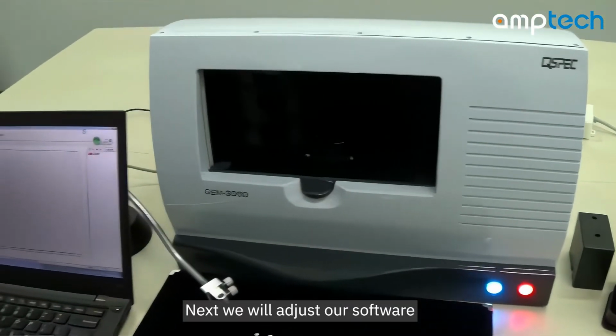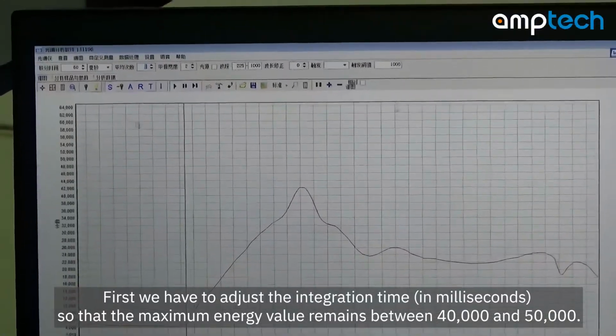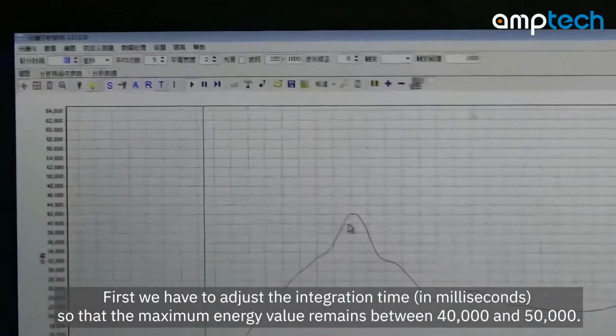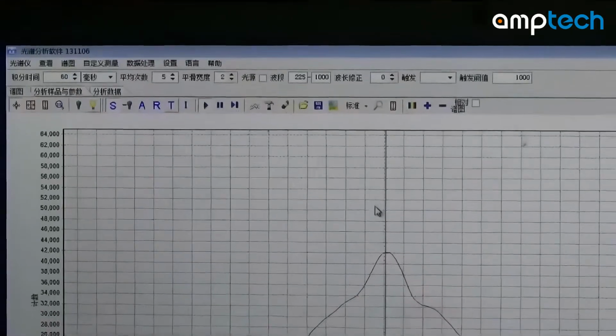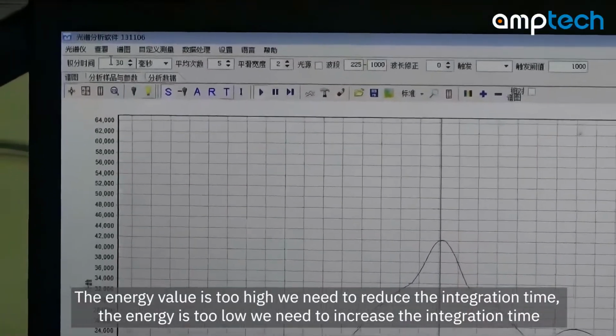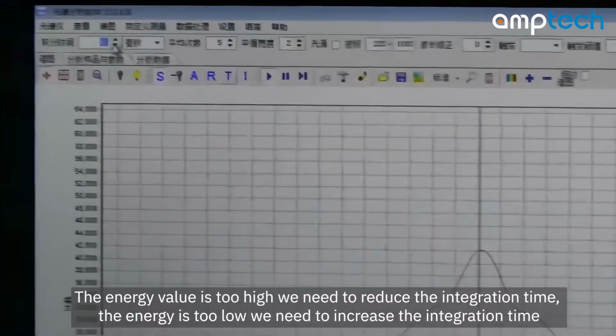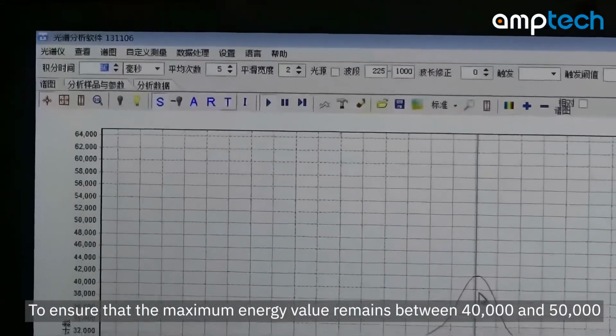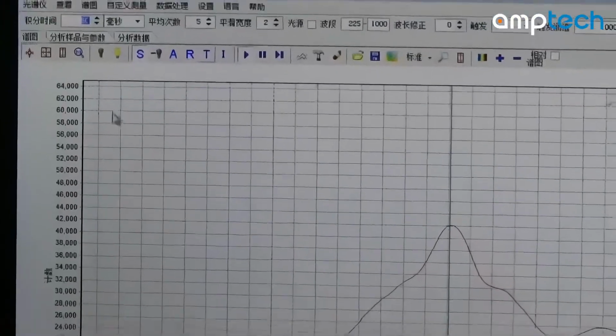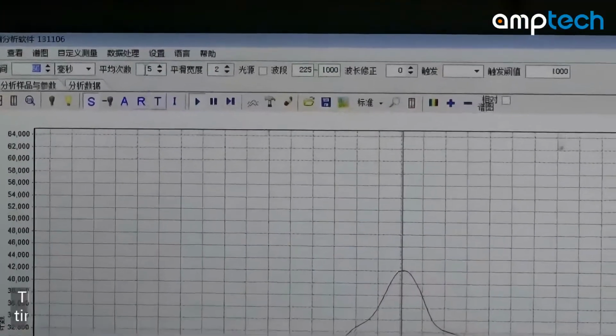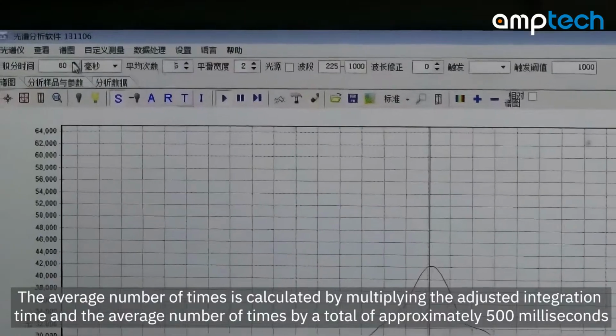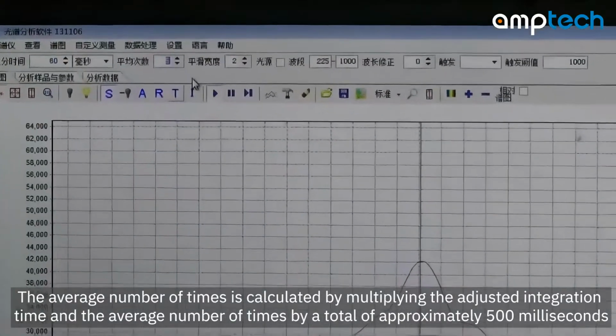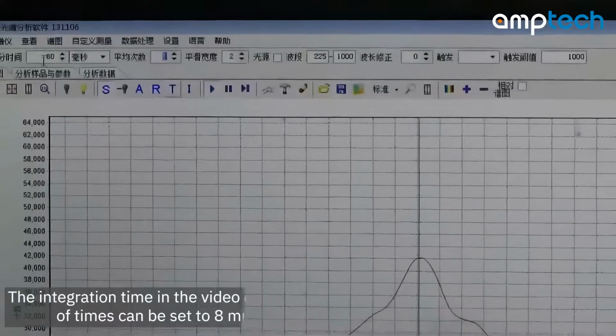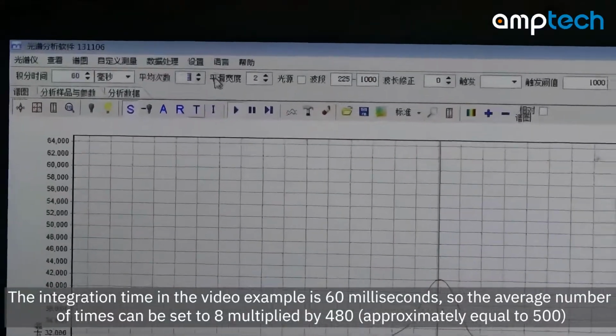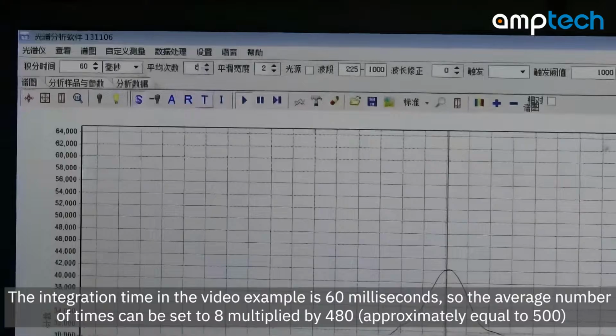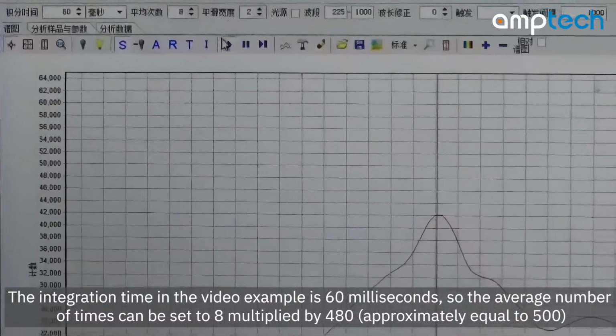Next we will adjust our software. First we have to adjust the integration time, in milliseconds, so that the maximum energy value remains between 40,000 and 50,000. If the energy value is too high, we need to reduce the integration time. If the energy is too low, we need to increase the integration time, to ensure that the maximum energy value remains between 40,000 and 50,000. Next we have to set the average number of times. The integration time multiplied by the average number of times should total approximately 500 milliseconds. The integration time in the video example is 60 milliseconds, so the average number of times can be set to 8, since 60 multiplied by 8 is 480, approximately equal to 500.